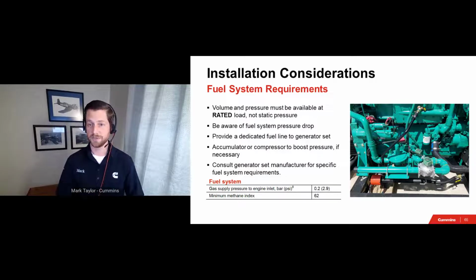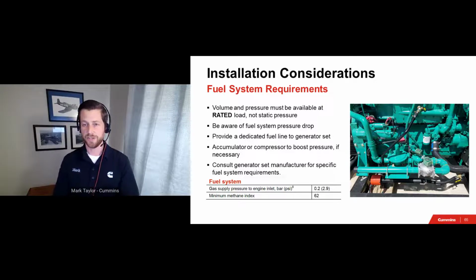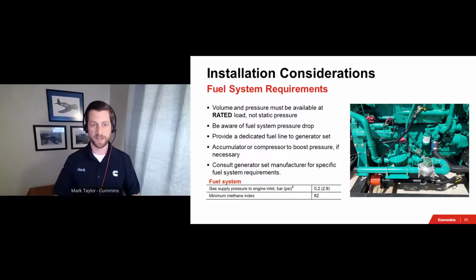Generally speaking, a diesel generator set is fine, so long as the fuel tank is close in proximity and full of fuel, of course. For a gaseous generator set, the key watch out is ensuring the gas supply can provide an adequate pressure and volume of fuel. Appropriate sizing of fuel lines needs to be done, factoring in all sorts of restrictions to flow, such as long runs of pipe and elbows. Ensure that the gaseous generator set is fueled by a dedicated gas line. That serves two roles: to isolate the generator set from potential pressure and flow fluctuations from other parts of the facility, and also in the event of an emergency, to allow the firefighters to maintain fuel flow to the generators when they need to shut off the gas lines for everything else in the building.